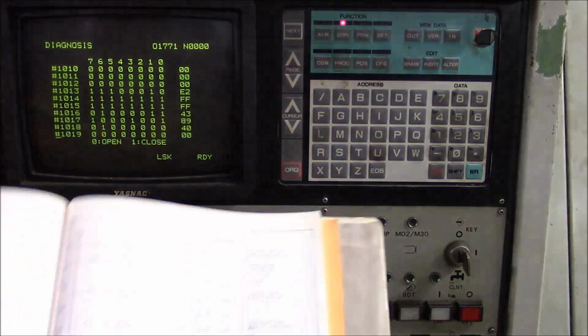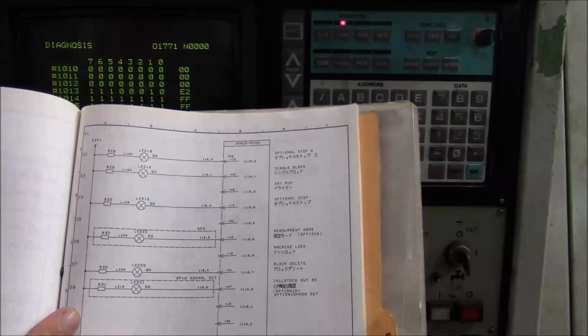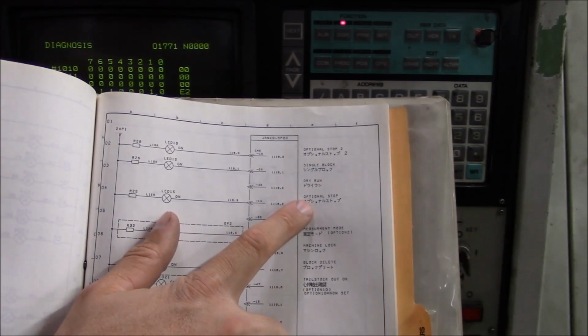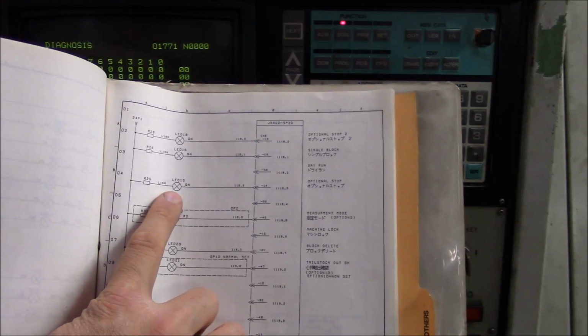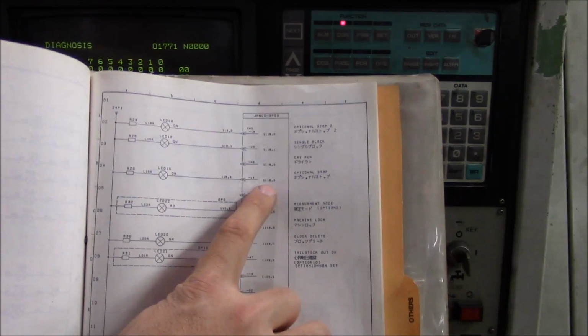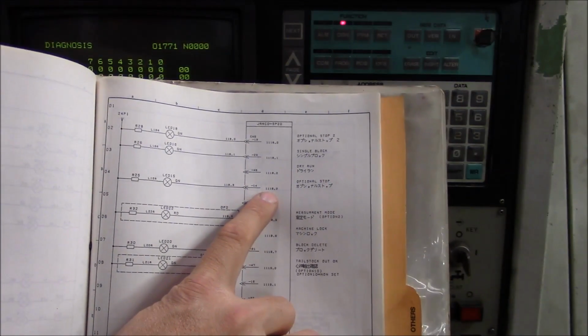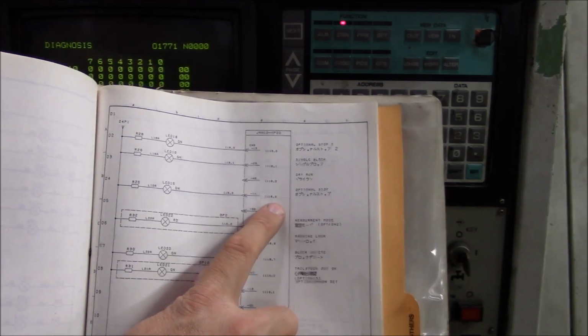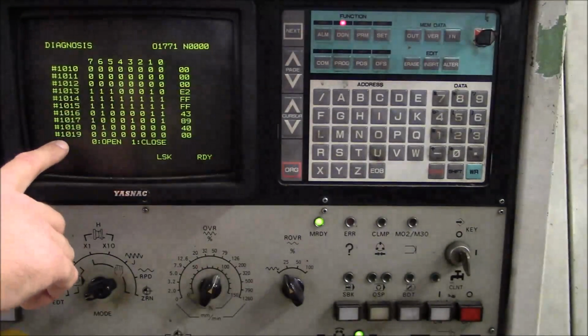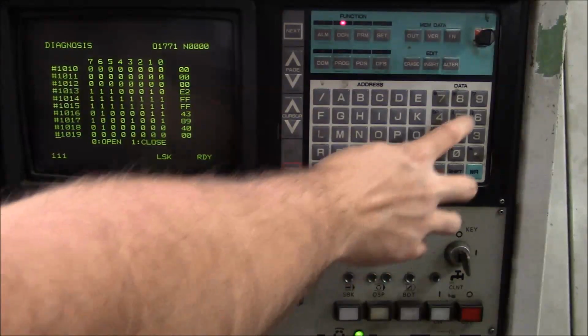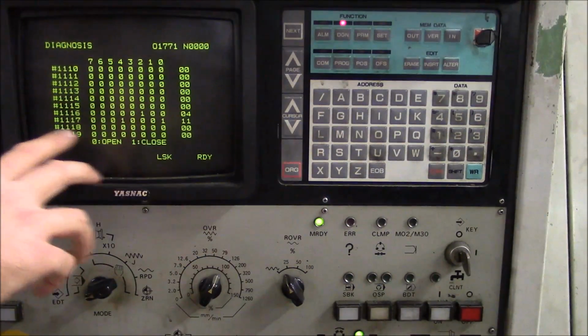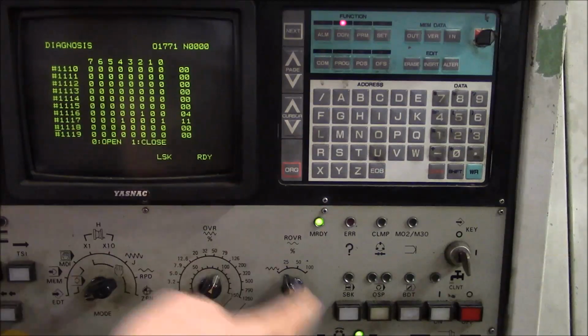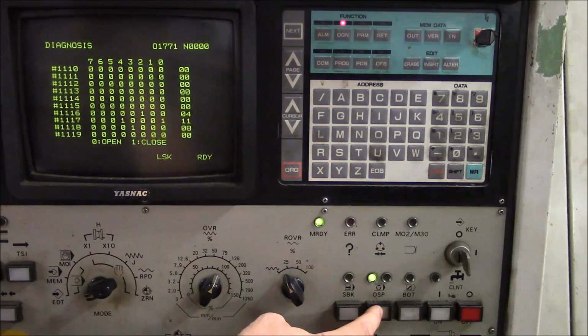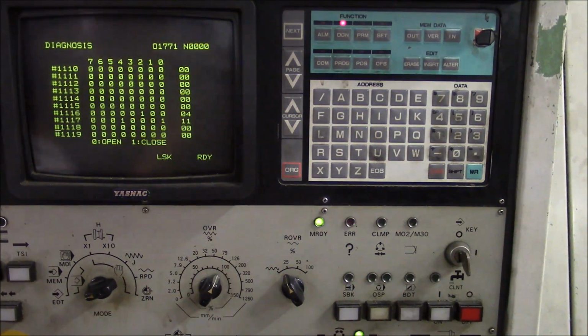Here it is. If we look at this page, there's optional stop right there, and it says LED 15. So there's a bit associated with that too, 1118.3. If we go back to our diagnostic page, 1118, cursor down, and monitor bit 3, we should see it come on as well, and it does. So that's the way you can use the diagnostic bits to troubleshoot inputs and outputs.